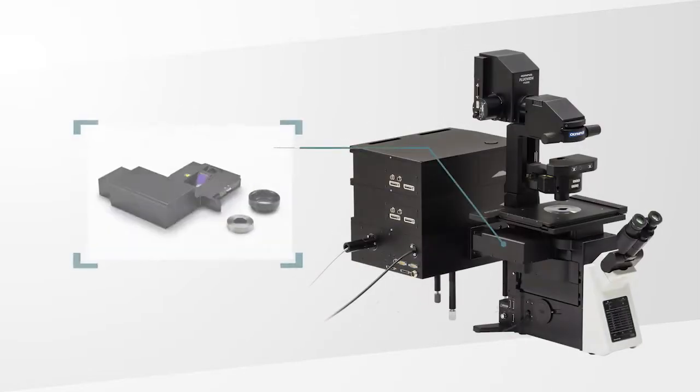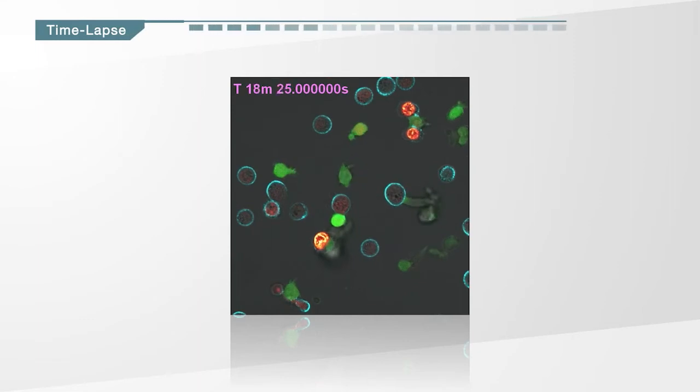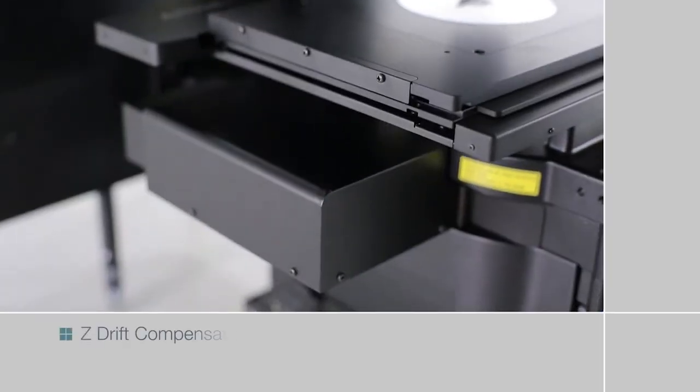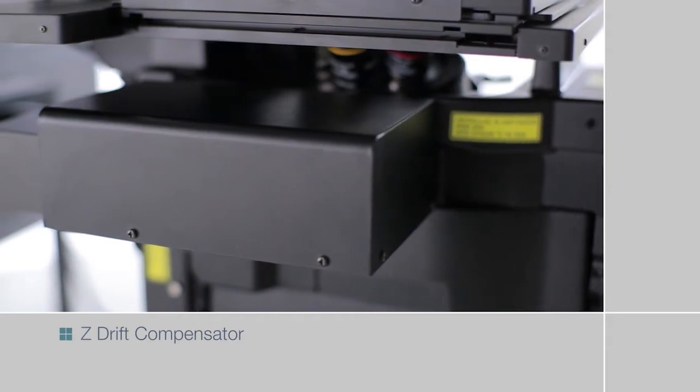The Z Drift Compensator uses a low phototoxicity near-infrared laser to keep samples in focus during long duration time-lapse imaging. The system corrects focus drift caused by perfusion, adding reagents, or temperature changes.